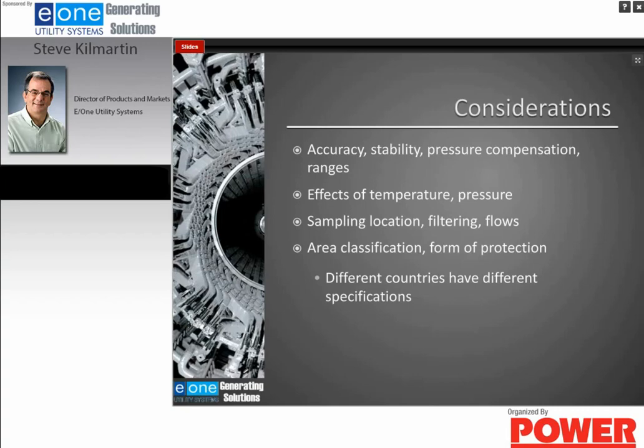The sampling location is not as critical as for a hydrogen purity analyzer. However, you don't want it downstream of filters. You don't want it downstream of a hydrogen dryer if you have a hydrogen dryer. You want the sample to be representative of what the hydrogen is in the generator.